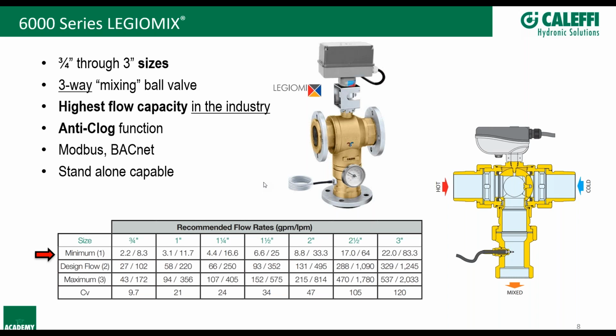Great question. So if you're designing this system appropriately, you need to have point of use mixing to make sure you're protecting those occupants during that thermal disinfection cycle. This is not something new, the idea of redundant valves in a system. Most healthcare facilities require point of use mixing valves anyways. And going back to the idea of Legionella and Legionnaires' disease, the biggest problem with Legionnaires' is for those who already have compromised immune systems, which again is going to be hospitals, healthcare facilities, nursing homes, things like that.